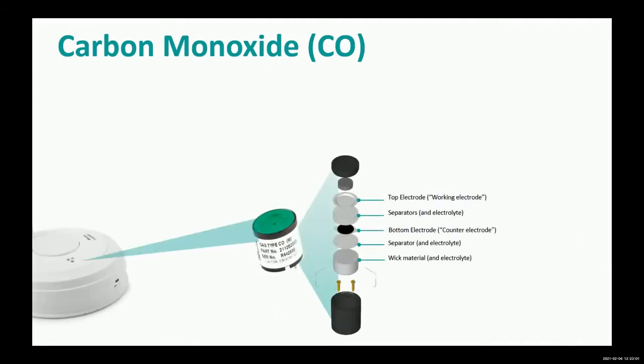So what you have here is a bit more intricate than the smokes or the heats. We have the CO sensor itself, and we've covered that with a green cover just to give a bit of extra identification on it. If you look at the middle of that sensor's green cover, you can see the small little hole, and that's the aperture that the carbon monoxide goes through. Underneath that, you have a graphite filter, and that stops an awful lot of dirt and dust and fibers that are in the atmosphere getting into the chamber, so it won't distort whatever's going on inside there.